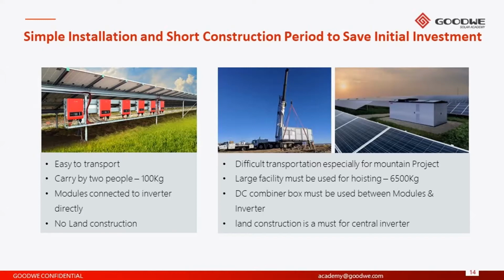And by simply installing on the back of the PV array, it brings more advantages in terms of protection. You can install the string inverters in a way such that they sit underneath the PV panels to provide a little bit of protection against direct sunlight, snow, rain, hail, and so what have you, in terms of the environmental elements.